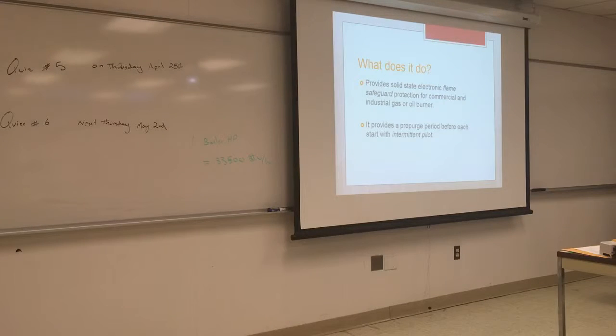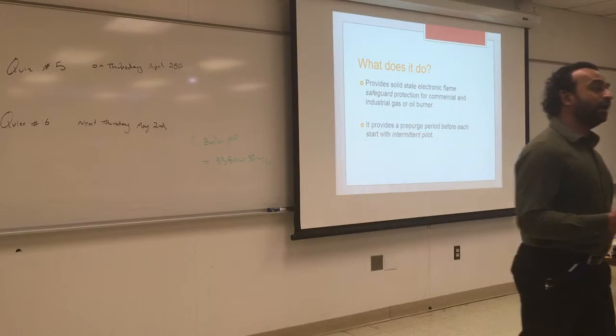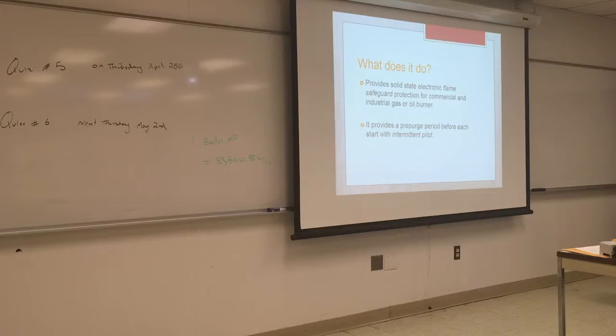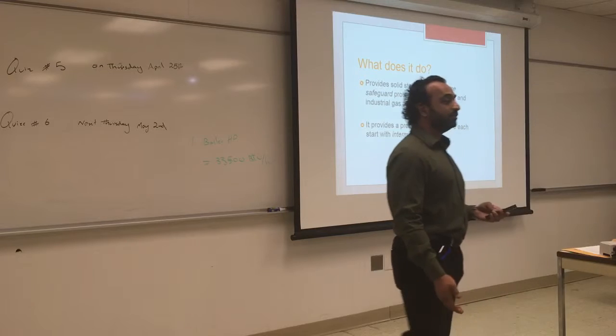So the post-purge and the pre-purge are decided based on the size of the chamber, the type of fuel, and what else? Type of fuel, how big the chamber is, and also how big of an inducer fan you have, and what the draft situation is. If you have a big draft, you can purge it faster.